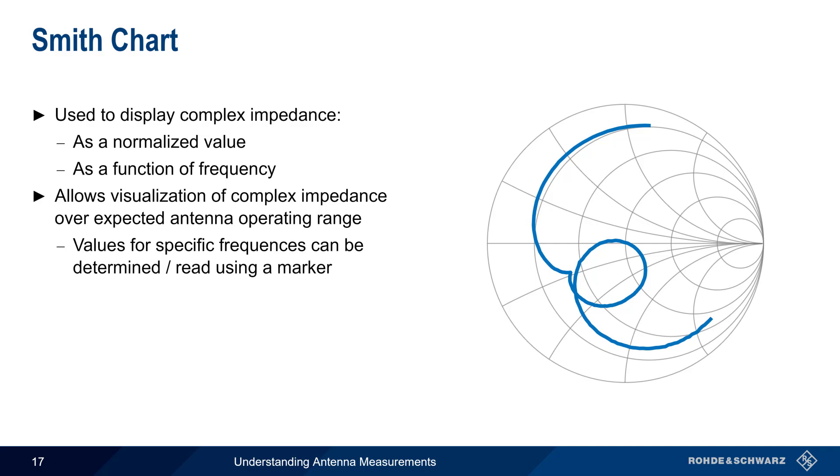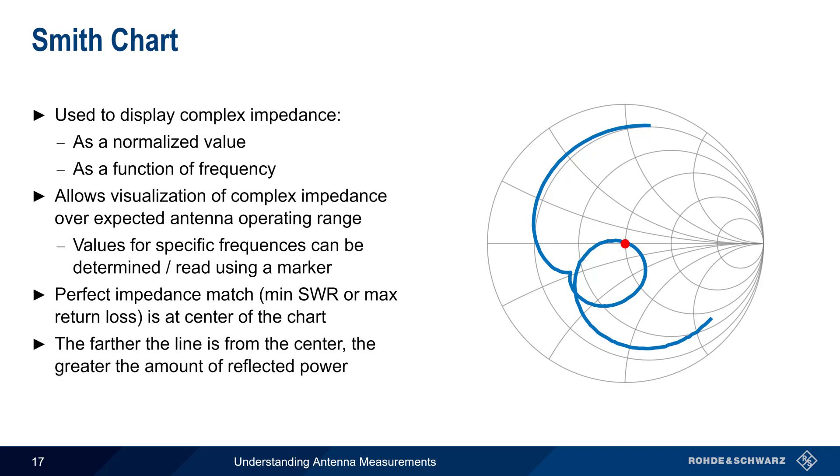Although we don't have time to go into detail on the Smith chart in this presentation, we can make two broad statements about measured values. First, the best impedance match, that is the minimum SWR or maximum return loss, occurs at the center of the Smith chart. And second, the farther the line or trace is from the center, the greater the amount of reflected power.